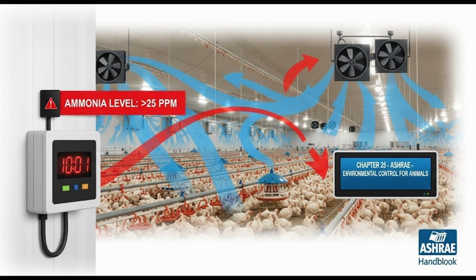So the inlets are crucial for distribution. Absolutely. Their size, shape, and location determine where the fresh air goes and how it mixes with the room air without causing drafts. There are also positive pressure systems, where fans blow air in, and neutral pressure systems, but negative is dominant for simplicity and cost.